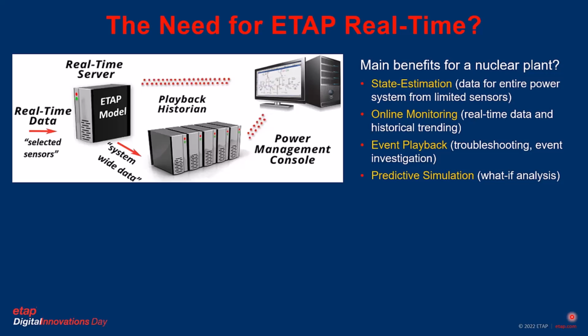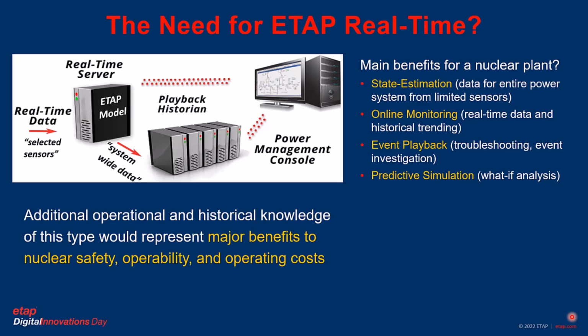So what's the need for ETAP real-time? Well, the main benefits for a nuclear plant are state estimation, that is, getting data for the entire plant system just from limited sensors. Online monitoring, having real-time data and historical trending. Event playback, the ability for troubleshooting and event investigation from the data that's stored. And predictive simulation or what-if analysis. Additional operational and historical knowledge of this type would represent major benefits to nuclear safety, operability, and operating costs.